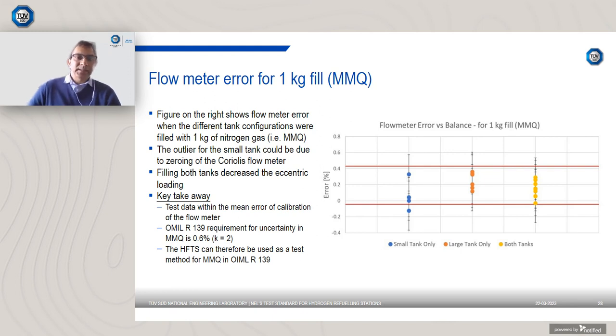So again, the key takeaway from this plot is that the data are within the mean error of calibration for the flow meter. And also because OIML R139 states that for minimum measured quantity, the maximum permissible error is doubled, you're looking at a 0.6% uncertainty. And as a result, the test rig can therefore be used as a test method for minimum measured quantity, as specified in OIML R139.